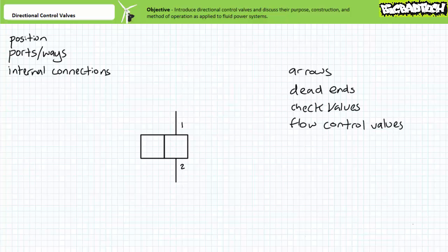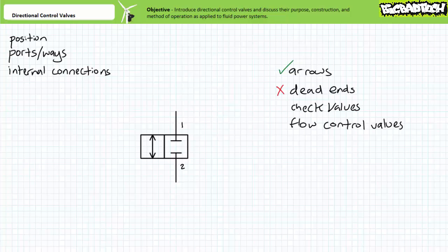Internal to the position boxes, directional control valves use a range of symbols to represent selectively connected or disconnected ports. Arrows from one port to another mean an open passageway is established between the two ports and fluid can flow. Unidirectional arrows mean flow is intended to be unidirectional, whereas bidirectional arrows mean flow can be bidirectional. A dead-end T means that port is not connected and no fluid can flow. Let's limit this introductory analysis to unidirectional and bidirectional arrows implying connection and dead-end T's implying no connection.